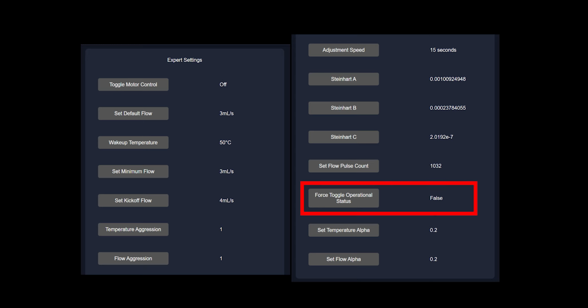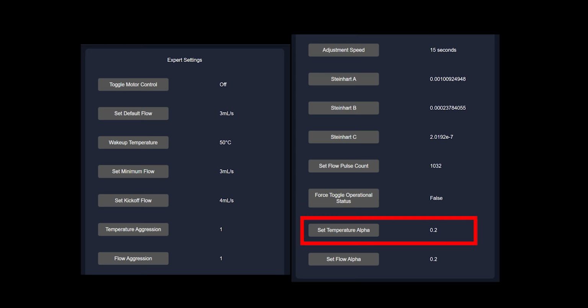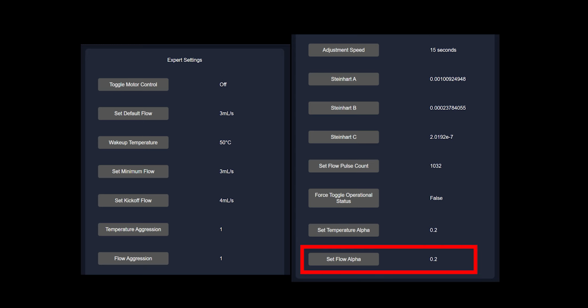Force toggle operational status is a switch that will simply force ATACC to go from standby mode to active mode, even if the wake-up temperature has not been met. This typically isn't used. The temperature alpha determines how smooth and stable the thermal probe reports its temperature to ATACC. The temperature is averaged to create a smooth reading and will filter out any anomalies or false readings caused by electromagnetic interference. The lower you make this number, the stronger the smoothing effect will be. The larger you make this number, the less filtered, but also more responsive it will be. The flow alpha is the same thing as the temperature alpha, except it affects the flow sensor instead of the temperature sensor.